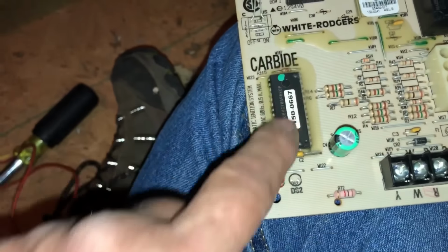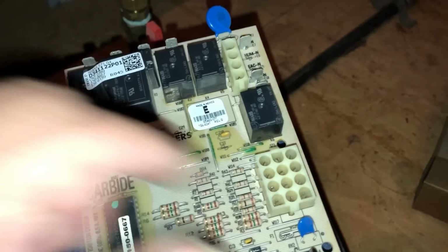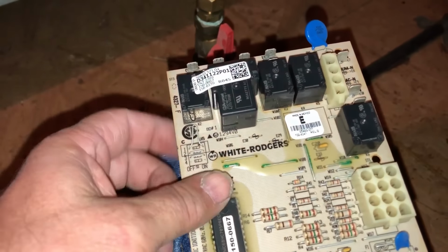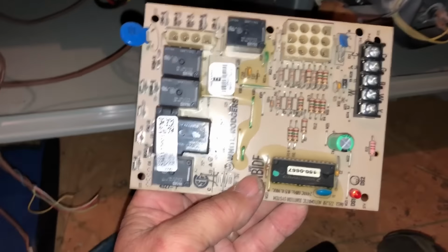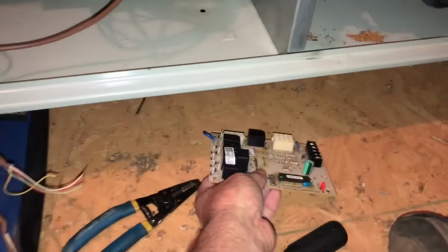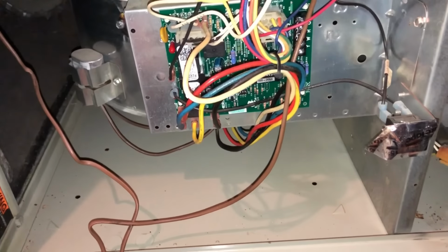I mean, it's possible this little electrolytic capacitor has something to do with it. This chip right here could have something to do with it. Those little ceramic discs, I don't know, that might not be a ceramic disc capacitor, I'm not sure what that is. But regardless, that is a common trait of these boards, especially if they got a little bit of age on them. They'll start falsely giving you the high limit error. So, all right, I think everything's good with this board.